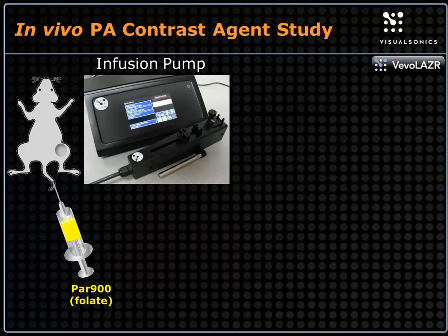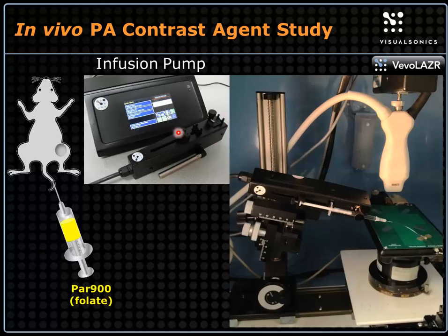Now to perform the injection, in the past, you've had to open the enclosure. You can't actually perform the injection with the enclosure open. The laser won't fire. So you'd have to image, open the enclosure, do the injection, close the enclosure, and then continue with your imaging. But we've got this infusion pump which allows us to do remote injections. So we can put this portion of the infusion pump, the injector itself, we can mount it onto the injector within the enclosure.